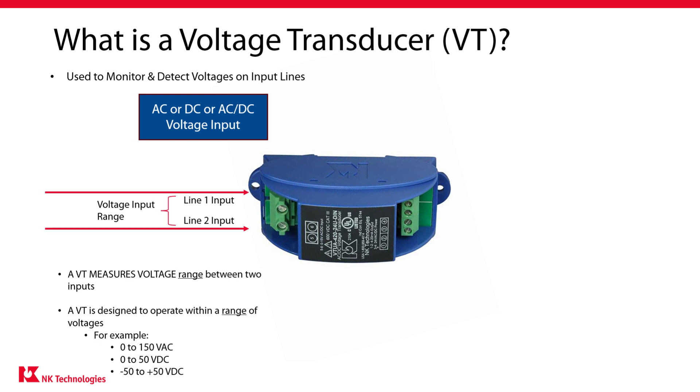Voltage transducers are designed to handle specific input voltage ranges across the two inputs. A monitored range might be from 0 to 150 volts AC, or perhaps from 0 to 50 volts DC. Some transducers will monitor a negative range — for example, you can measure minus 50 volts to plus 50 volts DC. This is useful if the voltage you want to measure is bidirectional. The key point is that there's an upper and lower range that can be measured.